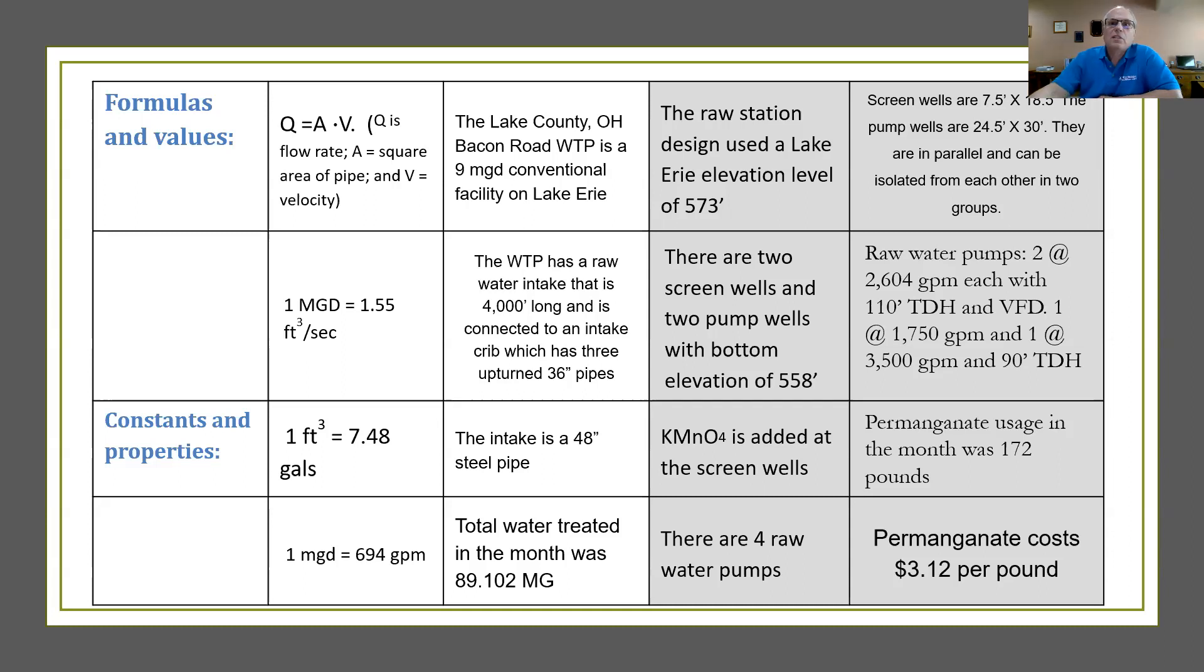Going to the next column we see that the raw station was designed at a Lake Erie elevation level of 573 feet. That's critical to one of the problems coming up. Now the water comes in through the intake and it comes into the raw water station where there are two screen wells and two pump wells. The water goes through the screens into the pump wells and each of those have a bottom elevation of 558 feet.